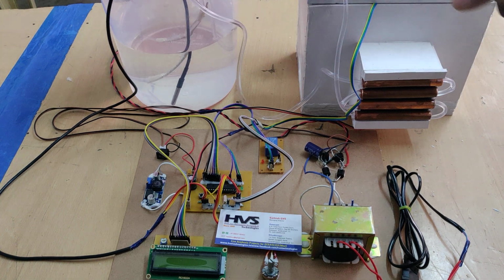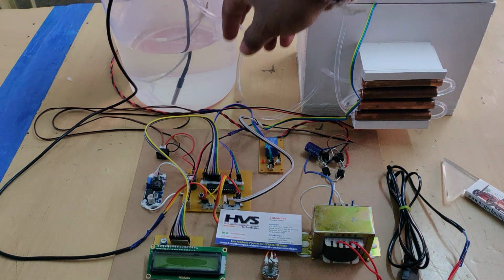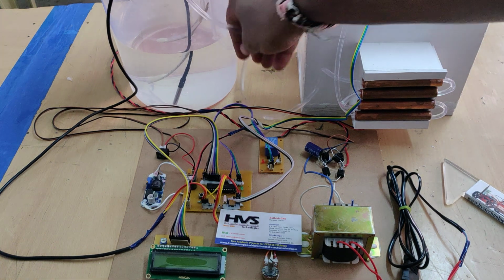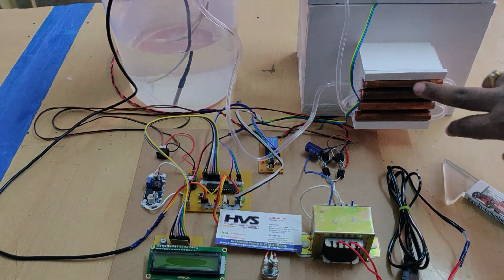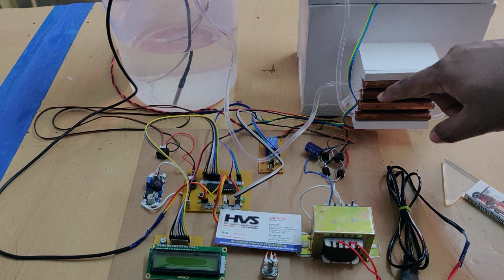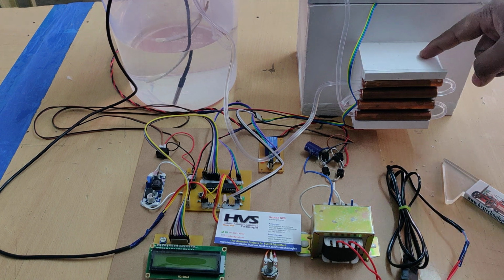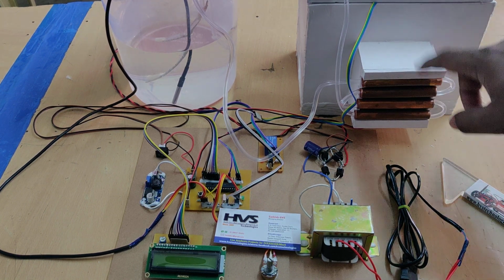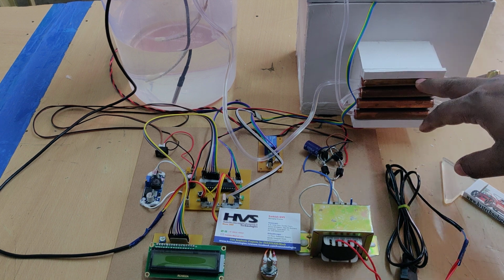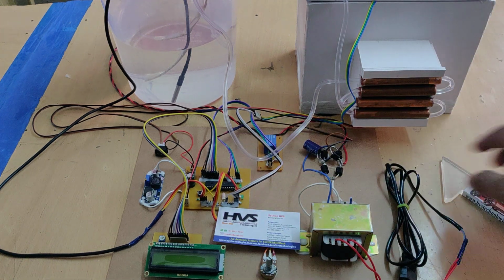And also we are going to cool down the temperature of this water by using this water circulation method. So we are taking the water with the help of this motor and pumping it through the pipe, through these copper pipes. When we are passing this water through the copper pipes, there is an exhaust fan over there which will take the heat from the surface of these copper tubes, so that the water inside will be cooled down, and that temperature is continuously measured by the controller, and it will check with the condition.